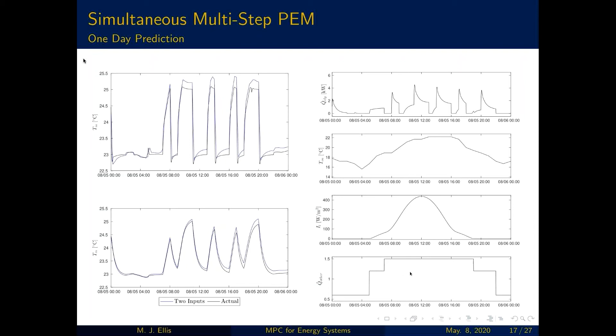Since this is simulated, we can extract the simulated building mass temperature. The upper two plots show the sensible heat load on the space, which is what the MPC would manipulate over a trajectory, and the outdoor air temperature, which we can forecast over a day horizon using available forecasts. The last two, solar radiation and internal loads, would not actually be available for forecasting purposes, but you can see their profiles in this simulated case.